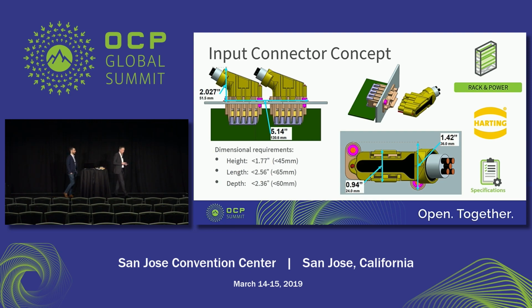All right, anybody else? Sure. What is the current rating? What is the temperature rise for the 50 amps? For the 50 amps expected, we have just finalized the according simulations on that. The temperature rise is somewhere around 50 degrees C. 50 degrees C. Yes. So it's not UL, it's more than UL. UL is a 30 degree rise. Correct. So it's a 50 degree rise. With the 32 amps, we are somewhere around 20 degrees C temperature rise.